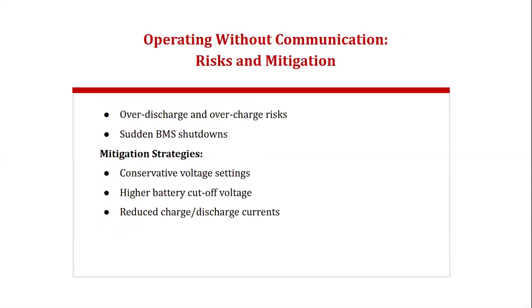Operating without communication, risk and mitigation. It has its own risk: over discharge and overcharge risk. Because there's possibility when you are operating without communication, and your inverter is capable of firing the battery, it can get overcharged. When you are loading it, you can get over discharge. But what do you do? That's where the mitigation strategies come in.